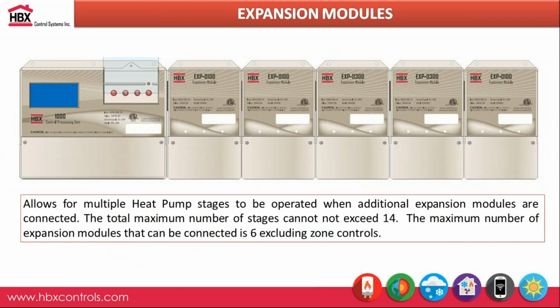So in terms of the modular expandability, as I mentioned before, the Eco 1000 can do up to 2 heat pump or chiller stages. If you needed to add on, for a system where it required 4 or 6 or even 8 heat pump stages, you would just add on these expansion modules. The way they connect just uses a 32-pin connector from the side of the controller to the main unit, and you can build these expansion modules up to 14 stages. In terms of expansion modules, you can only have a maximum number of 6 if you're using the EXP-0100, and with the 300, you can only go up to 6 as well. So keep that in mind.